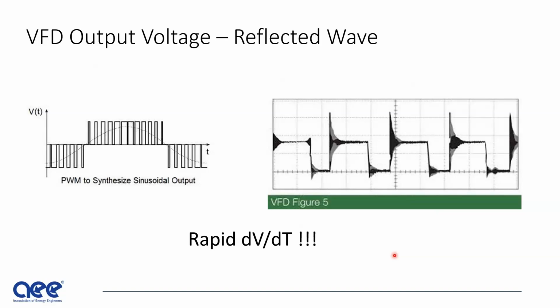And here's why we need these tools. We're looking at things like rapid dV/dt. Here, if we look at the synthesis of a sine wave over on the right, you see that you have these on-off transitions on the IGBTs that create 5 megahertz ringing waves. These 5 megahertz ringing waves can be propagated down a VFD cable, the cable between the VFD and the motor. And when they propagate, they can resonate. And when they resonate, they can create very high voltage that's at least 3 times the DC bus. On a typical 480 volt motor, that's 1800 volts.